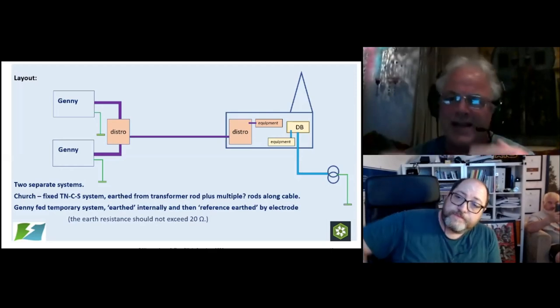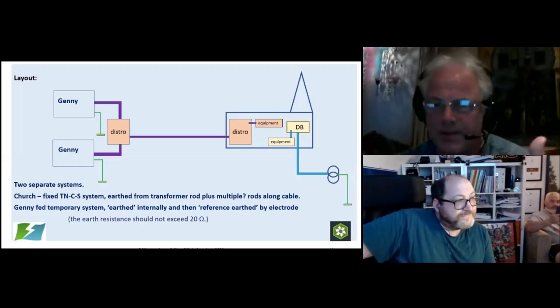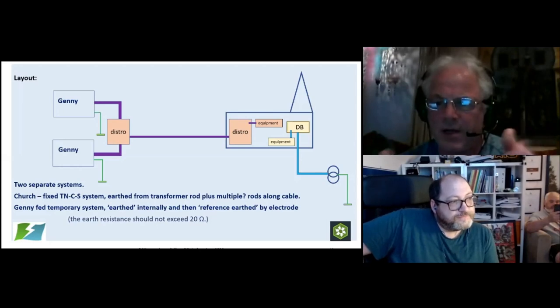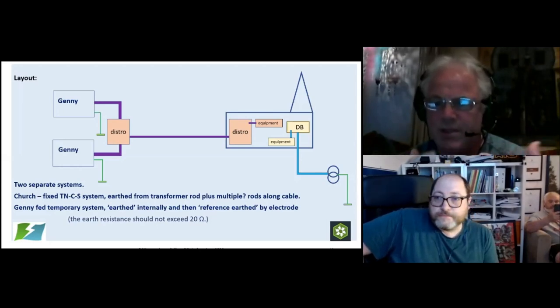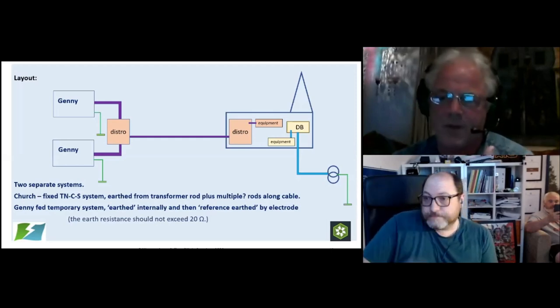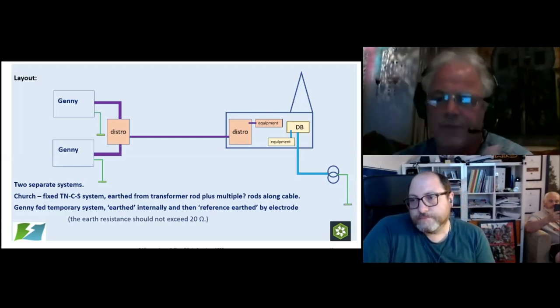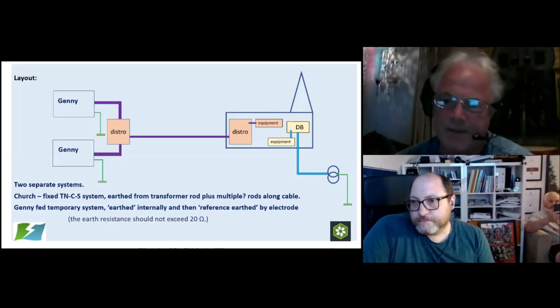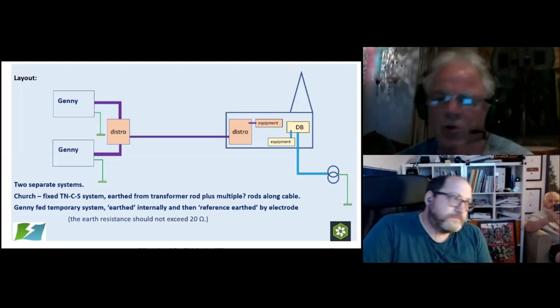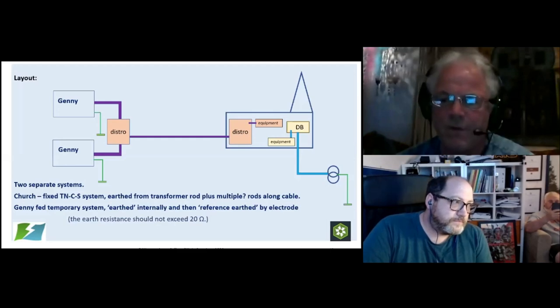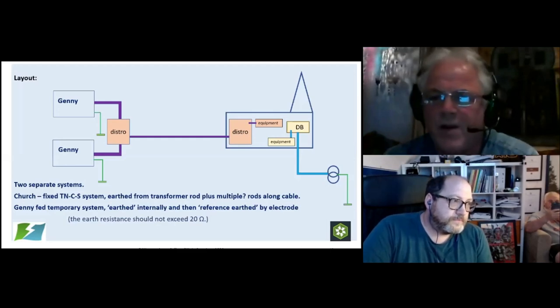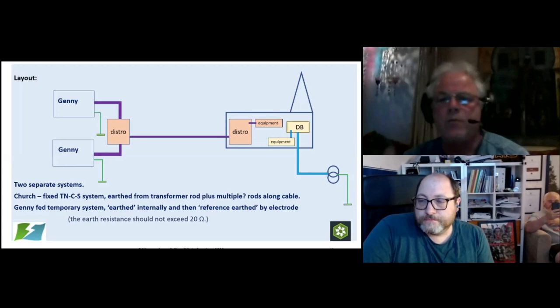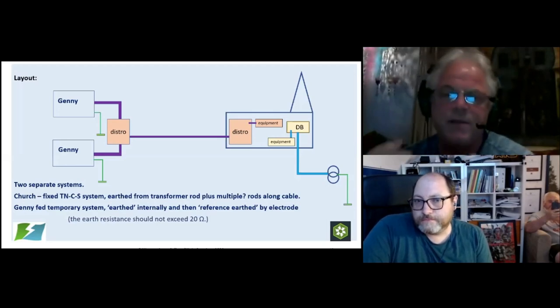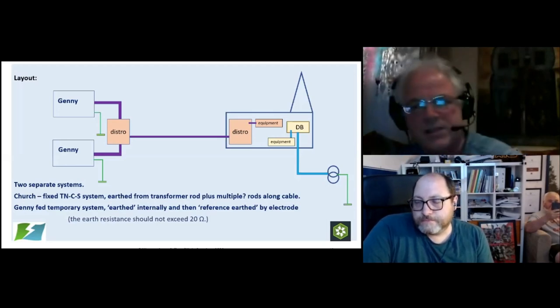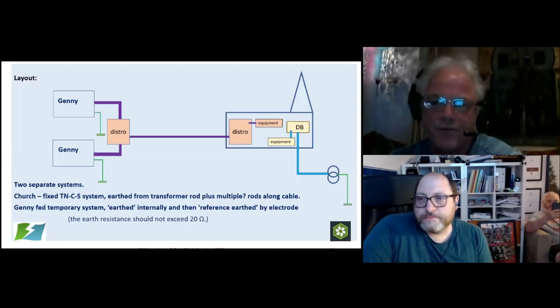And again, this is one of these things where I always try and go back to basics. We've got an electrical system here off the generator. If there is a fault on a piece of electrical equipment which is connected to that system, the fault path will be back through the electrical system coming from the generator. Yeah, the fault will always try to return to its origin. The fault current will, because that's the natural way for it to go. Same with the fixed installation, any fault on there, the fault path should be back through the fixed installation. That's the natural direction for it to go.